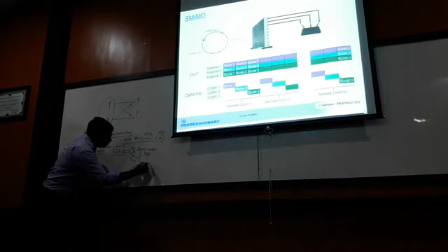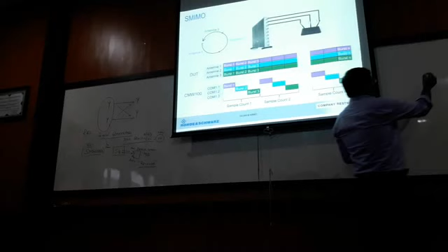To test the receiver of the device. The other part is that the device also has a transmitter. So how do you analyze the signals transmitted from the device? The phone transmits. For that you need a spectrum analyzer. Here you have the device under test, whatever you are developing or designing. It has multiple antennas, antenna 1, antenna 2. Then you need a spectrum analyzer, wherein you give the signal to the spectrum analyzer to measure. What you measure is maybe the power, and then modulation characteristics like dBm, error vector magnitude, magnitude error, say for example frequency error, and then spectrum measurements. So this is for transmitter, TX measurements.